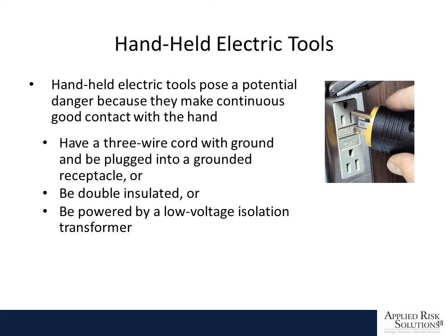Handheld electrical tools are at serious danger because your hands are in contact with them, and you're most probably standing on ground when you're doing it. There are certain things that must take place here. You must have a 3-wire cord or ground to plug it into. It must be double insulated, and it should be powered by a low voltage isolation transformer. Anytime you're outside or working around water, you should always be using a ground fault circuit interrupter in your circuit to protect you from a handheld electrical shock.